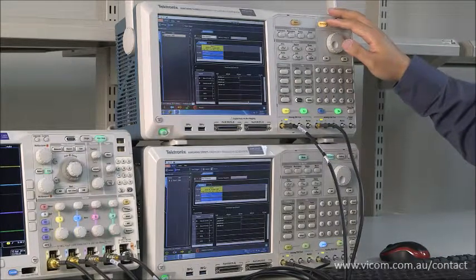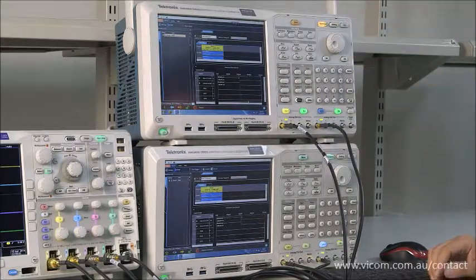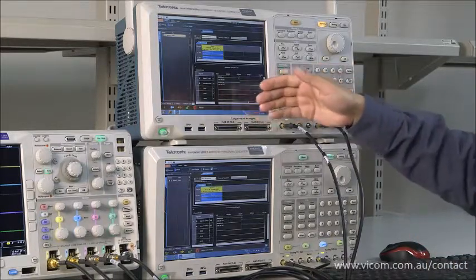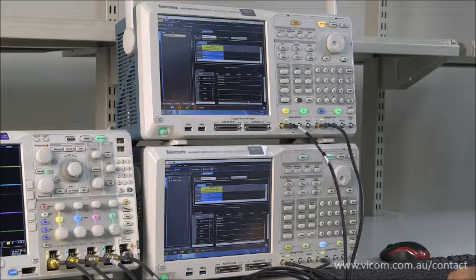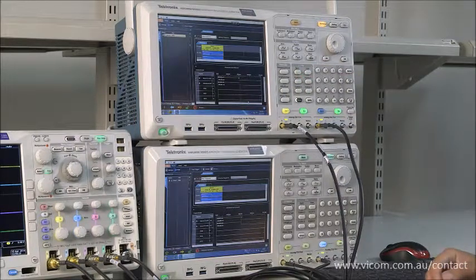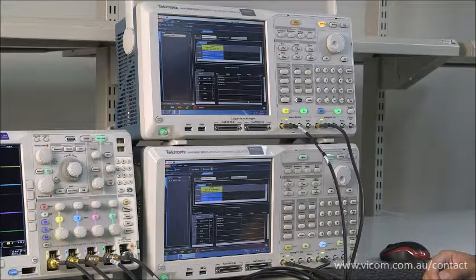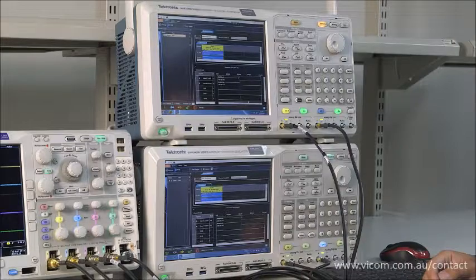While in advanced mode, or the AWG mode, the two analog channels and up to 32 digital channels can work synchronously on variable sampling clock and in sequence mode. And to synchronize multiple units in advanced mode is extremely easy.